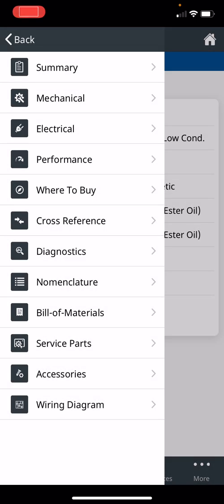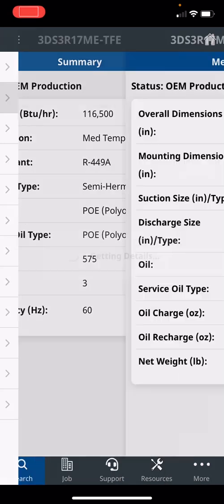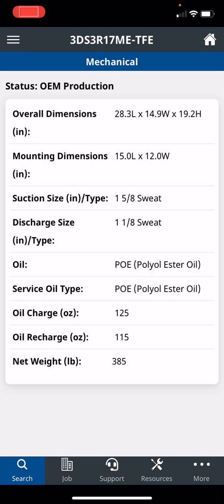From the contractor point of view, the most important things I'm going to show - there's going to be many more things in this app, but I'm going to show you the most important things as a technician. In mechanical, here it tells you the suction and discharge size, and it says sweat, so you know this is a brazed compressor. If you needed a muffler on that compressor, you would know the size. If you needed a discharge check valve and you forgot the size, you know it for this compressor.